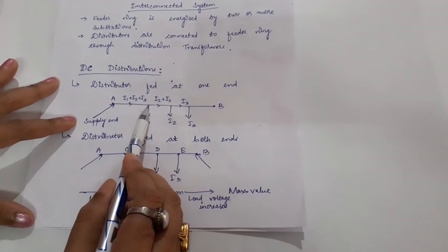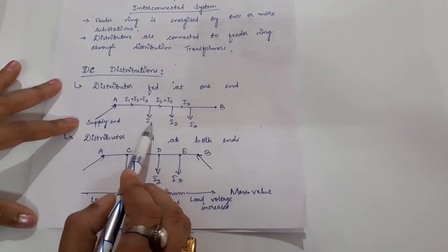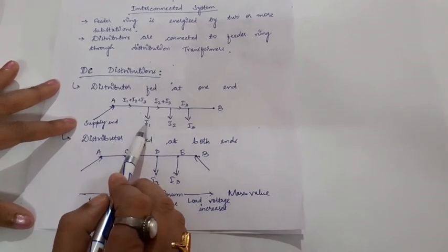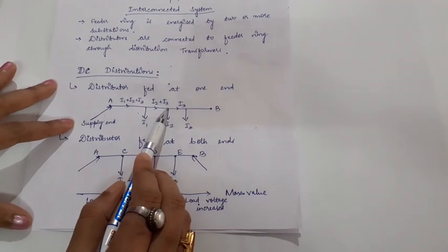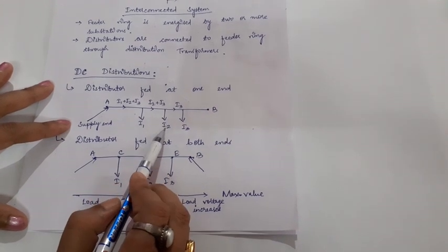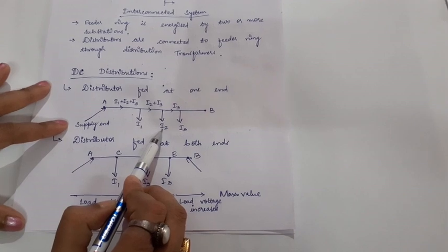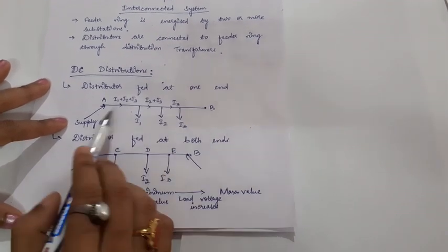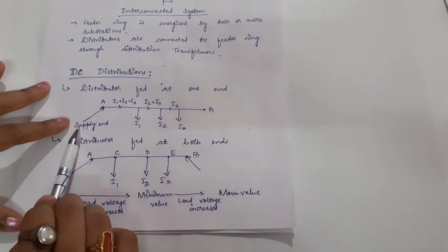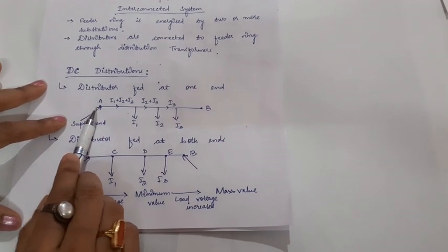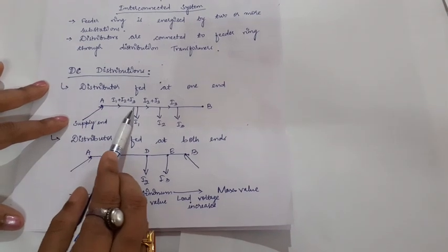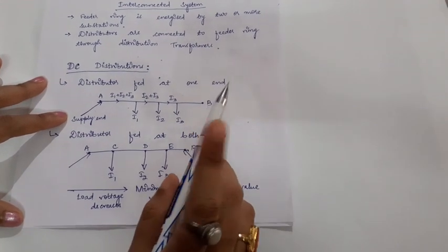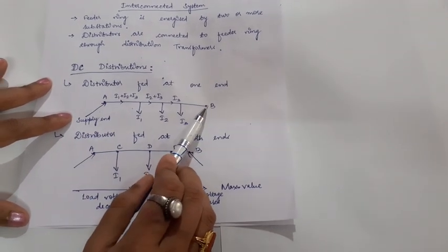Tappings or loading is done at separate points. At the first point, current I1 is tapped off. When I1 is subtracted from the phasor sum of I1 plus I2 plus I3, the remainder current passing through the distributor is I2 plus I3. At a separate point, current I2 is tapped off. The remainder current I3 is then tapped off at another point. In case of distributor fed at one end, the load voltage at the supply end is maximum and goes on decreasing as we move towards point B, where the load voltage is minimum.